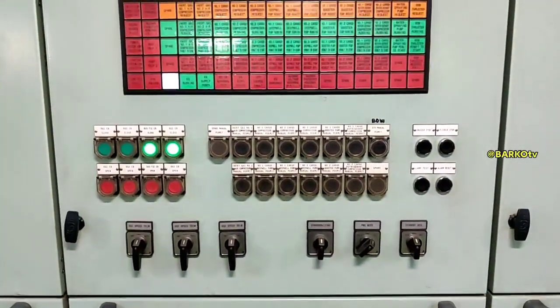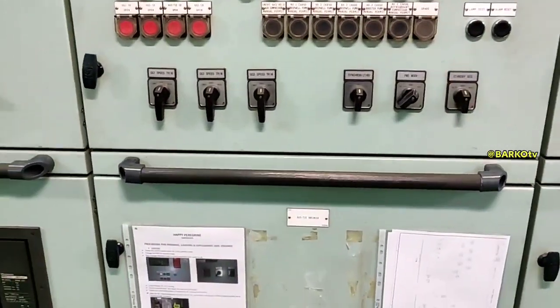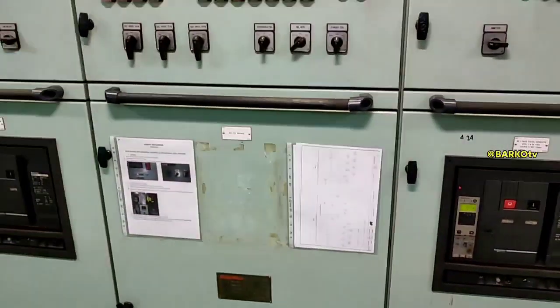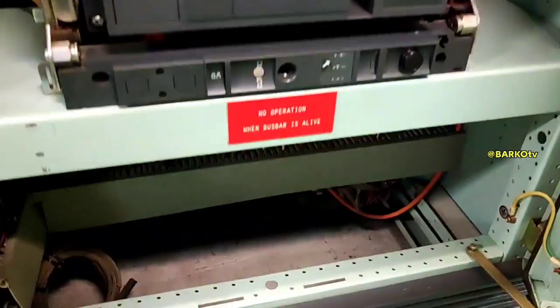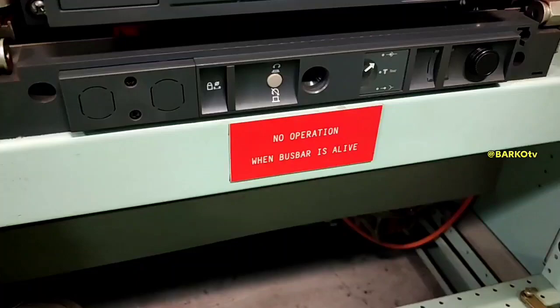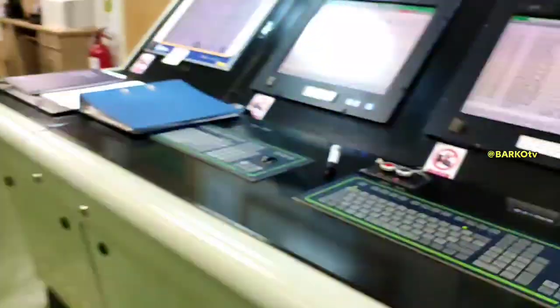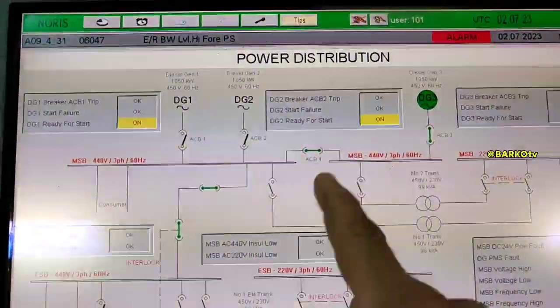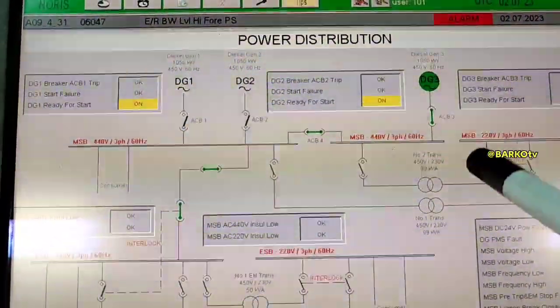These are our instruments: synchroscopes, kilowatt meters, and the governor with a switch mode for auto and manual. This is the ACB4 connecting from bus bar one going to number three. If you want to disconnect it — for example, for maintenance on DG3 — you can disconnect that ACB4.